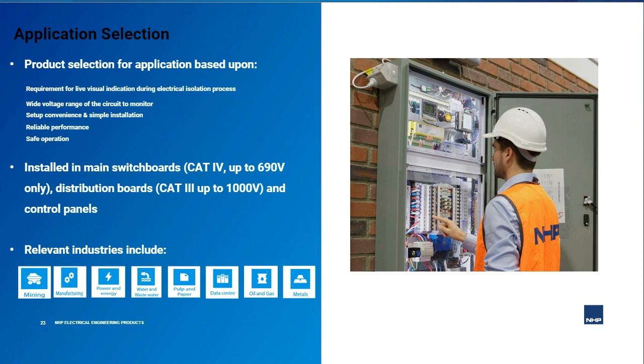It helps that a unit has undergone rigorous testing, which provides a high degree of confidence in it. You want it to be safe for the operator to use. Remember, you are working with dangerously high voltage levels. Therefore, that electrical isolation between the main monitoring unit and display unit is important.